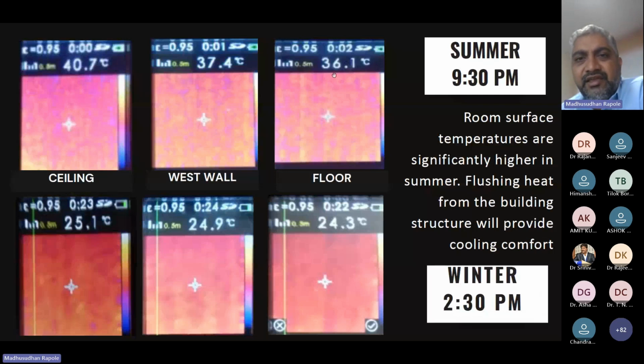So let me go back here. If you see all the ASHRAE documentation, everywhere they talk about operating temperature, because that is what we experience. We experience the net result of the mean radiant temperature and the dry bulb temperature of the space. So let's say in this space, the air temperature is 24 degrees centigrade, but the surface temperatures are, let's say, 37, 38 degrees centigrade. And let's say operative temperature is a mean function of MRT, mean radiant temperature, and this. So 24 plus 38 divided by 2, that'll be what? 30 degrees centigrade will be your operating temperature. Right? 30 degrees is what you are experiencing. That is the operating temperature. But you are thinking that you are experiencing 24 degrees centigrade because you are looking at only the dry bulb temperature.